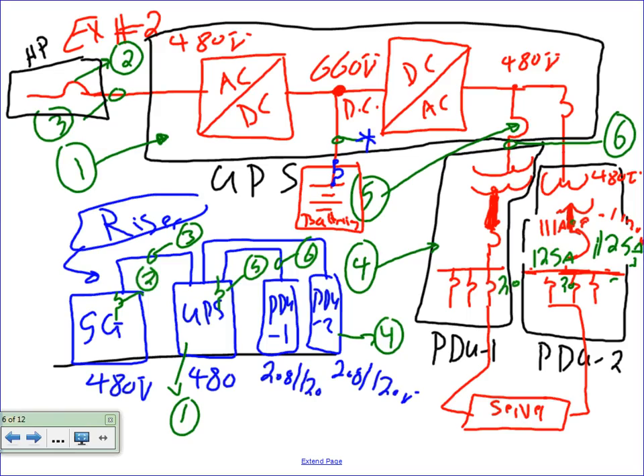Now, what's the difference between a PDU and a panel, Chad? Well, it looks like this panel, right? The difference between a PDU and a panel, guys, is a major difference. A PDU is like a substation. It has a transformer inside it. Almost always, they come with a transformer inside it. So you take the 480 down to 208. That's major. The second one is what they call 200% neutral. So they size the neutral double the phase because of harmonics.